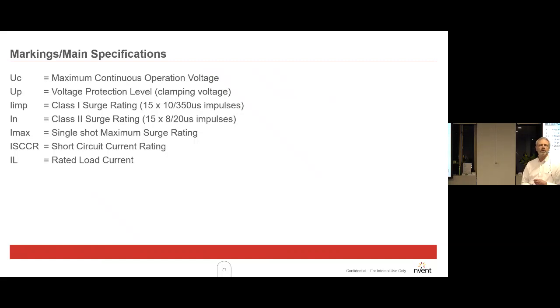I impulse is the surge rating, class 1 surge rating, and that's saying that it will take a quantity of 15 of that size surge before it fails. And IN is the class 2 surge rating of the same thing, the size surge it can take 15 of before it fails. IMAX is the single shot surge rating, and so those are important factors. When you're specifying surge protection, it would be good to see that written into the specification, what you're after.